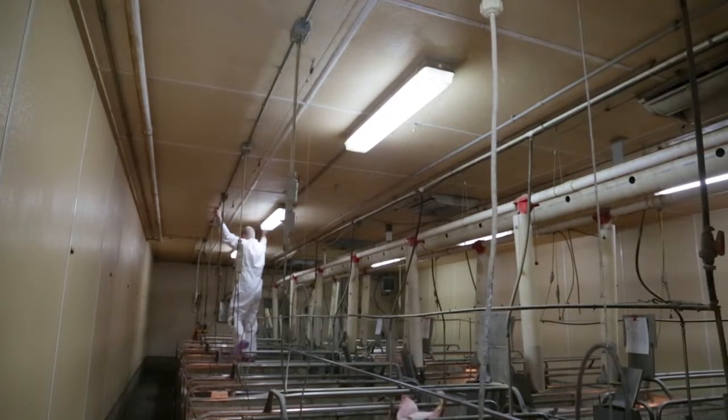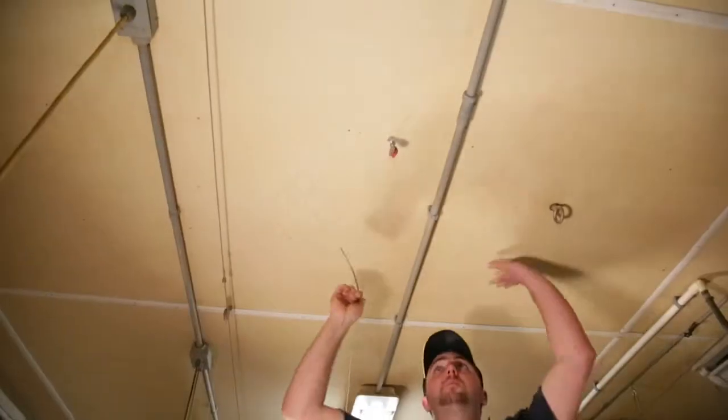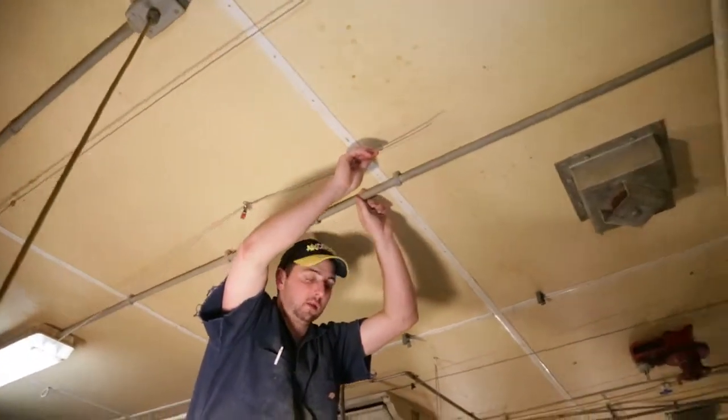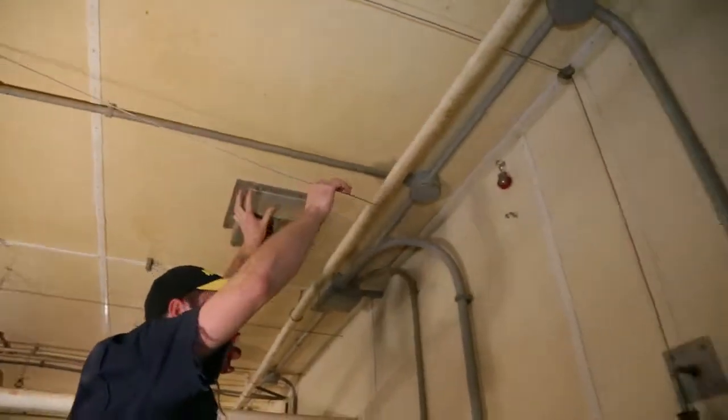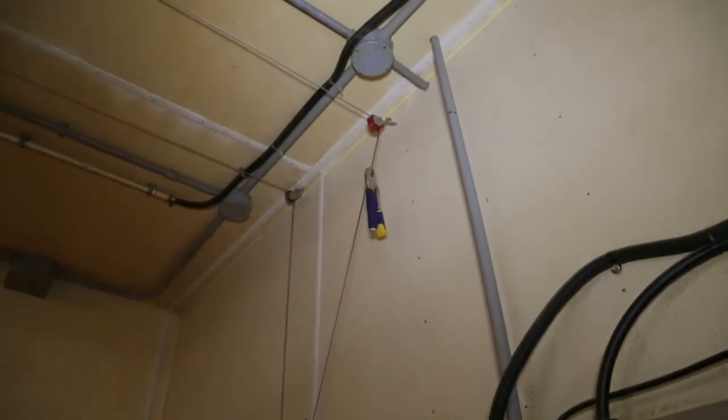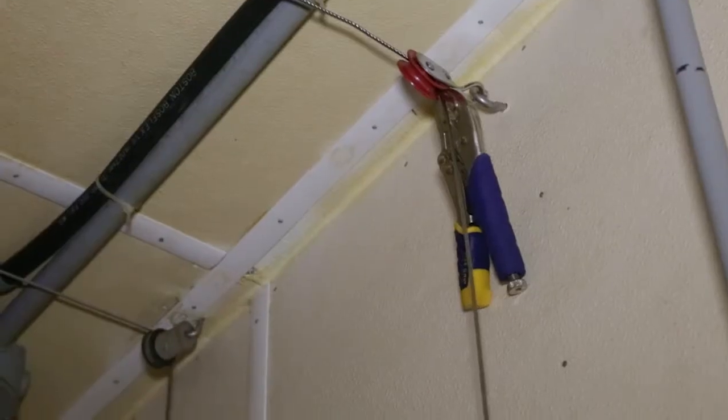The cable provides lift for the corona pipe runs. Pull the cable through the eyes of the pulley supports. Do not allow the cable to rub on other objects. Once enough cable is pulled for the furthest corona pipe run, cut an extra 10 feet of cable and tie or clamp the last to the end corona pipe support.